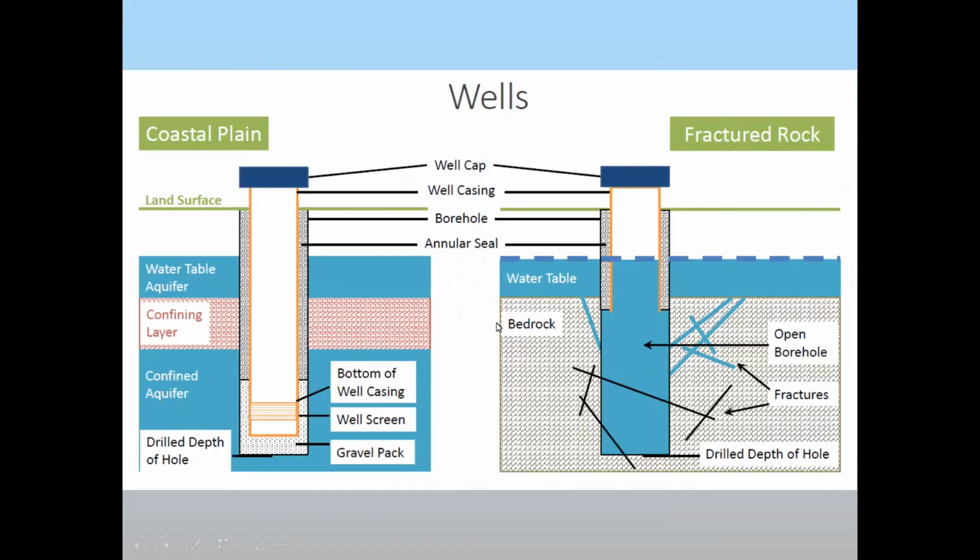So the wells, the actual design of the wells will vary dependent upon the type of geology that you're located in. This is the coastal plain well, which has the casing going all the way down into the confined aquifer here, and then has a screen, and that screen is designed to reduce the intake of sand particles, for example. In contrast, a fractured rock well has an open borehole.